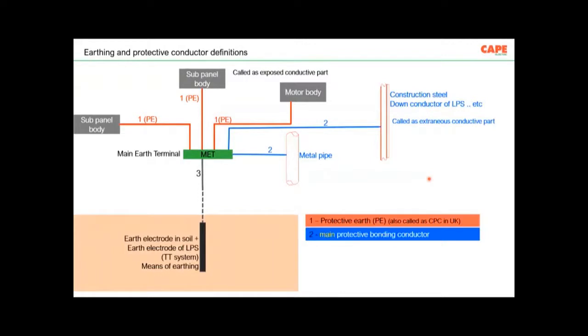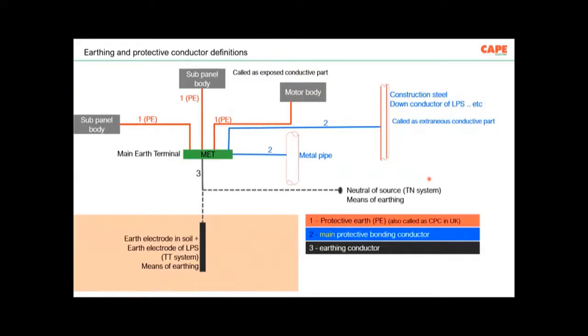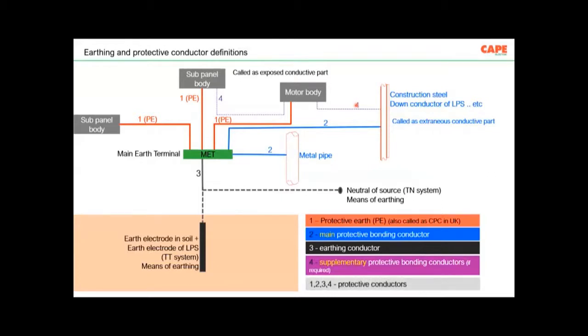Now, the MET is connected to an earth electrode in soil in case of a TT system. And these wires are called earthing conductors. The same MET is connected to the neutral of the source, which is also called an earthing conductor, in case of a TN system. And both the source neutral and the earth electrode are called means of earthing. And an electrical installation also requires number 4, which is a supplementary protective equipotential bonding. All these connections together are called protective conductors. So basically, whatever you are seeing in the picture is called protective equipotential bonding. Every building is supposed to have this kind of protective equipotential bonding, and this is called the equipment earthing. But you can just imagine whether you are connecting your metal parts such as handrails, such as the aluminum facade frame and all to your earthing system.